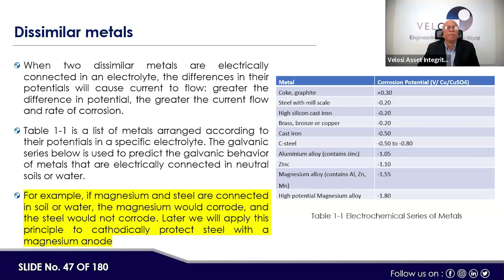Dissimilar metals like brass and steel pipe can be galvanically coupled. If they're connected together, there could be a flow of electrons from the high potential to low potential metal - one would act as anode, the other as cathode. That's why galvanic corrosion can take place in these kinds of scenarios.